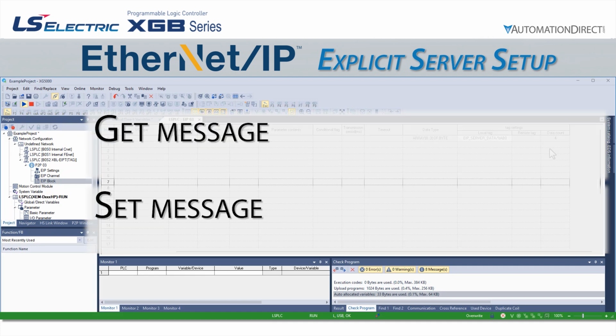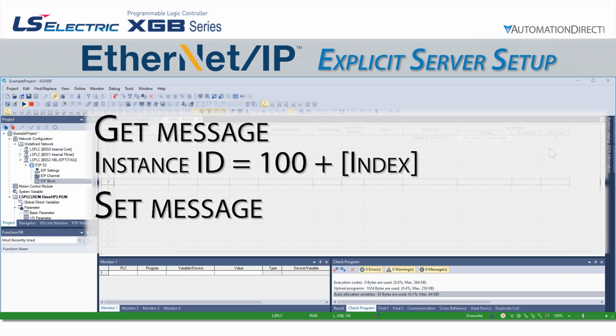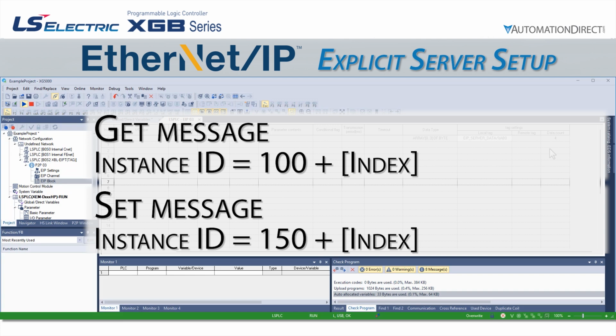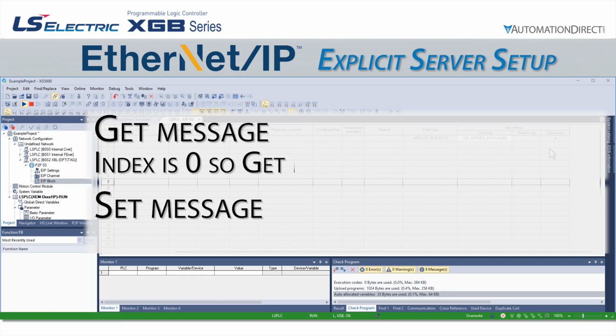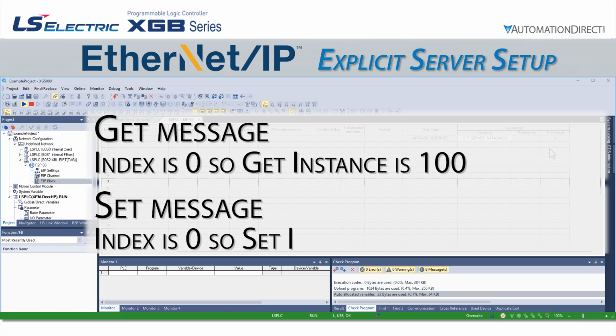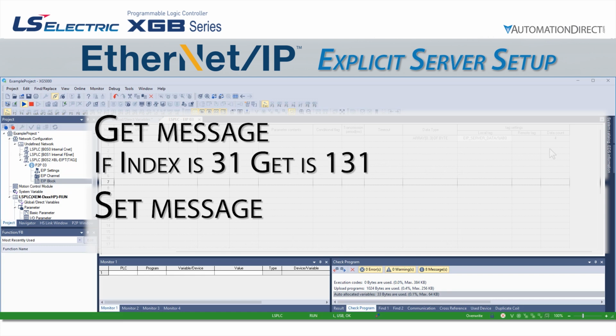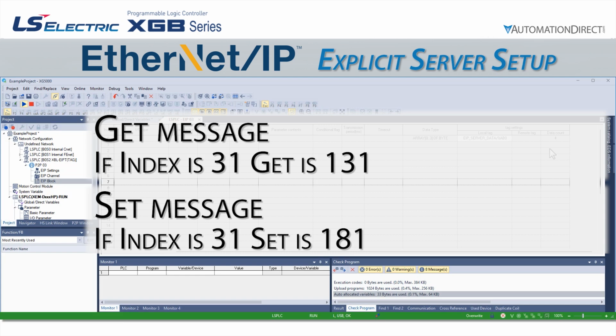The instance ID will depend on the index number in this EIP03 tab. For a GET message, the instance ID will be 100 plus the index number, and for a SET message, the instance will be 150 plus the index number. In our case, the GET message instance ID would be 100, and the SET message would be 150, since we only have one value. If we had information in index 31 we wanted to access, it would be available at instance 131 for the GET, or 181 for the SET.